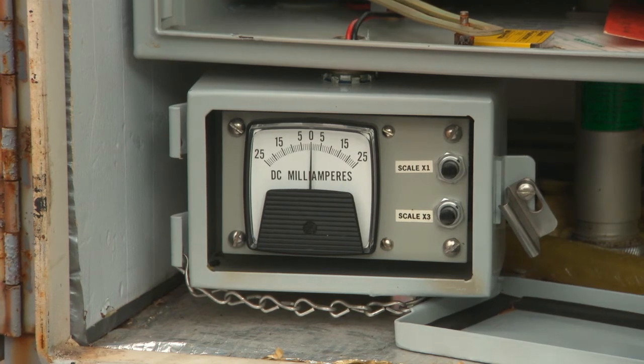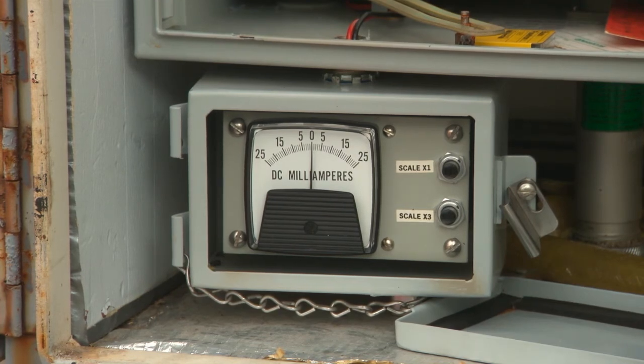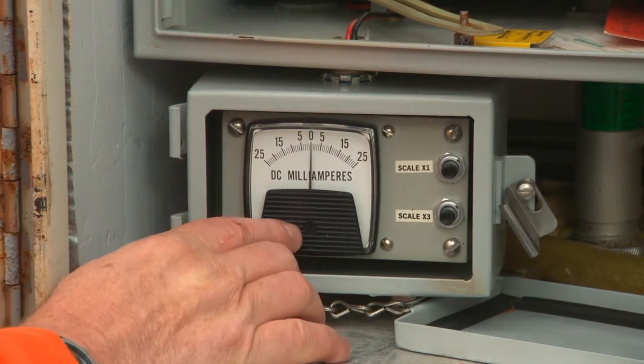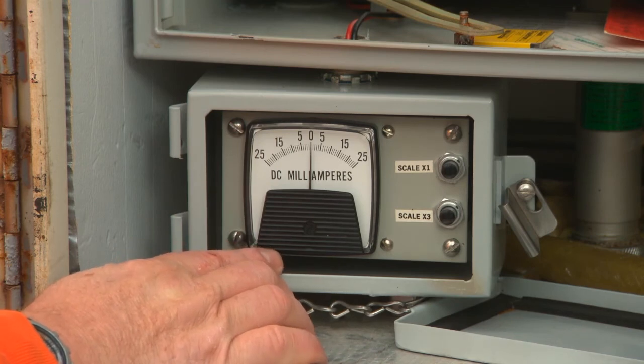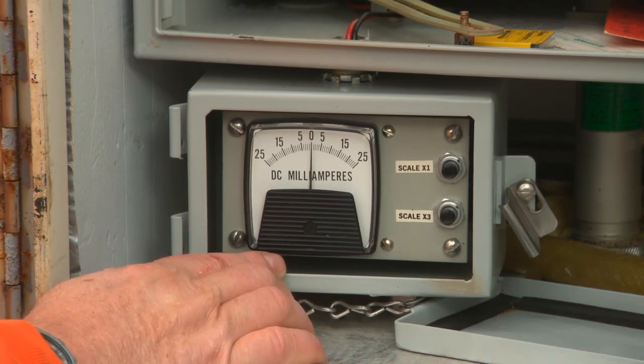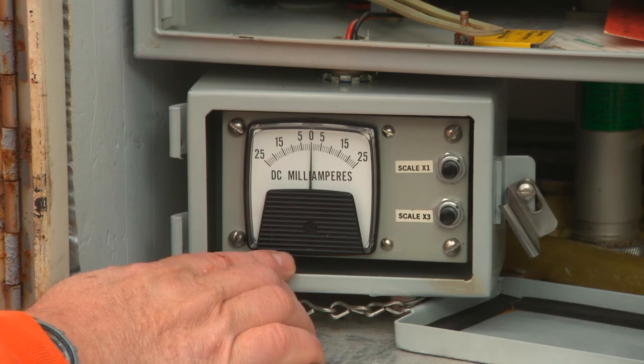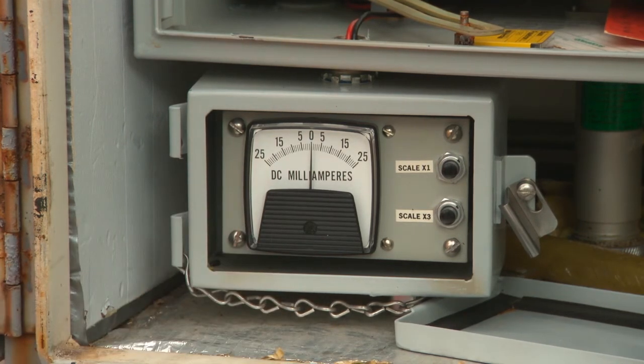When performing testing procedures, you'll notice a drain on the battery. If this remains on, your battery is beginning to deplete. The DC milliamperes display is for evaluation of your battery and charger. In a test position, you'll notice a certain draw on your battery. This will raise the milliamps deflection. When the batteries are fully charged and in good condition, you'll see a minimal trickle charge applied. While under normal operating conditions, if you notice the display is above a trickle charge, your batteries are beginning to wear out and require replacement.